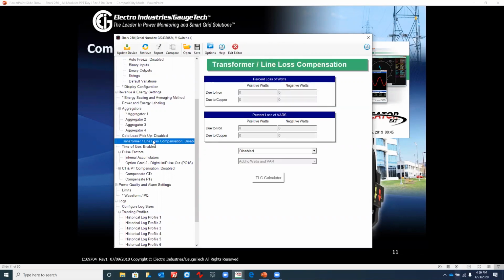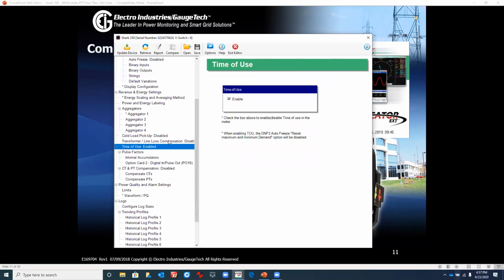Transformer loss compensation is something that we will get into tomorrow. It is a subject that is very important. Obviously there's line loss compensation and transformer loss compensation. Those are the most important ones. But we'll talk about that tomorrow. Time of use, we mentioned that briefly. We could get prior billing. We could get time of use schedules, rates, and so on by enabling the time of use function. And so that's where you would enable that function.